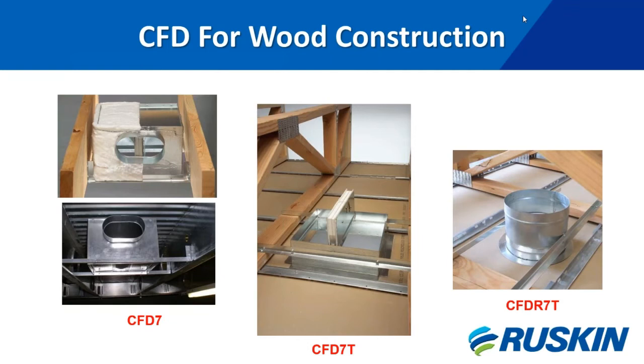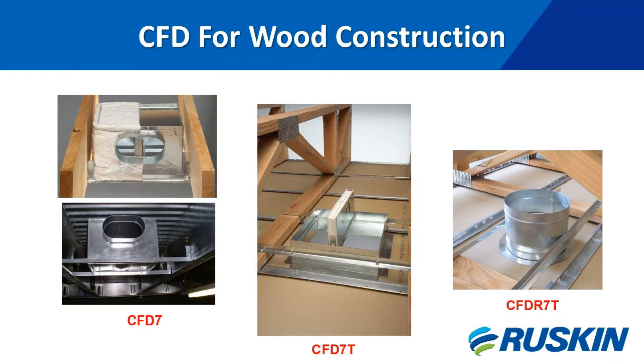For wood construction, the CFD 7 is a rectangular damper designed to be installed in either 2x10 or 2x12 solid wood joists. The CFD 7 is also UL listed for use in steel channel joist assemblies. Additionally, the CFD 7T is designed to be installed in wood open-web trusses. The CFDR7T is the same open-web truss type damper but a true round ceiling radiation damper for wood construction.